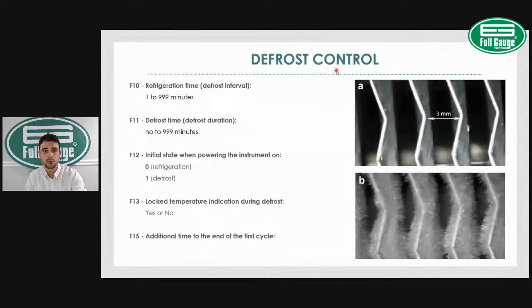Here's one thing. Let's suppose we have the system running, with 6 hours of refrigeration and 30 minutes of defrost duration. After 4 hours of refrigeration, we have a power failure. Whenever power comes back on, if the controller is set to start on refrigeration, that 6-hour cycle will start from the beginning. But we had 4 hours of refrigeration before that. So now we're going to have a total of 10 hours of refrigeration, which might block the evaporator.